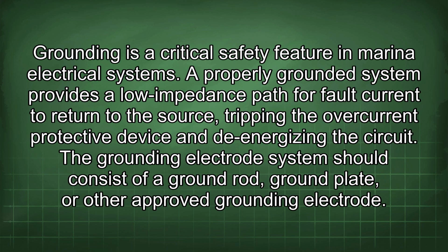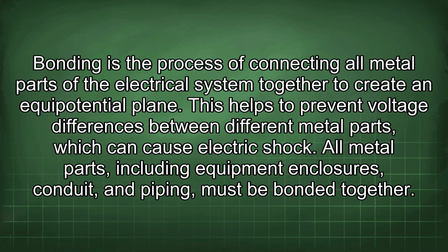Grounding is a critical safety feature in marina electrical systems. A properly grounded system provides a low impedance path for fault current to return to the source, tripping the overcurrent protective device and de-energizing the circuit. The grounding electrode system should consist of a ground rod, ground plate, or other approved grounding electrode. Bonding is the process of connecting all metal parts of the electrical system together to create an equipotential plane. This helps to prevent voltage differences between different metal parts, which can cause electric shock. All metal parts, including equipment enclosures, conduit, and piping, must be bonded together.